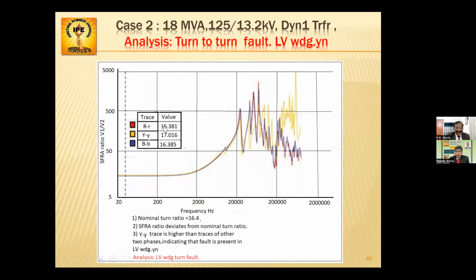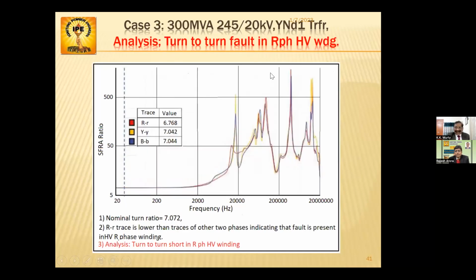So in this case, R to R will be 16.381, Y to Y is 17.016 and B to B is 16.385. Here you will see that the Y curve has gone up. The nominal ratio is 16.4 and the SFRA ratio deviates from the nominal ratio. So the Y to Y trace is higher than the traces of the other two phases, indicating that the fault is present in the LV winding. That is why the analysis is LV winding turn fault. And for a turn to turn fault in HV winding, the curve will be like this.